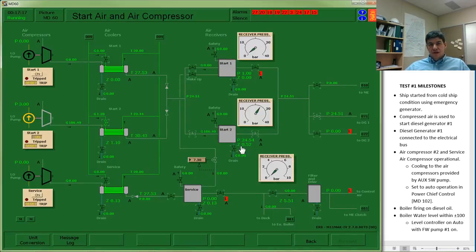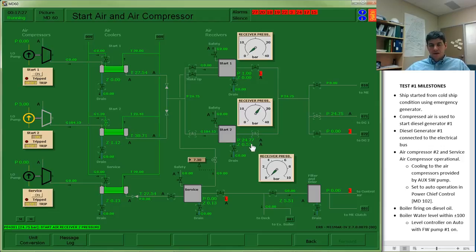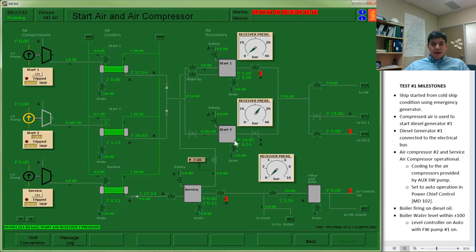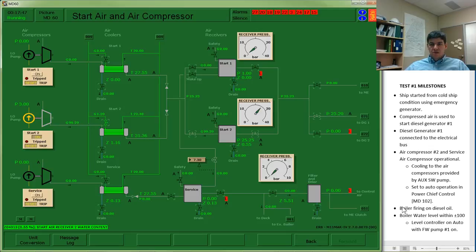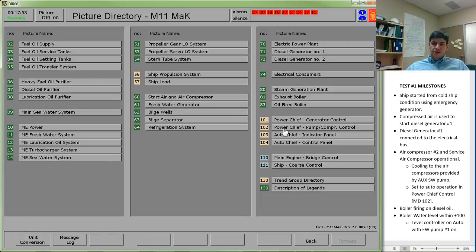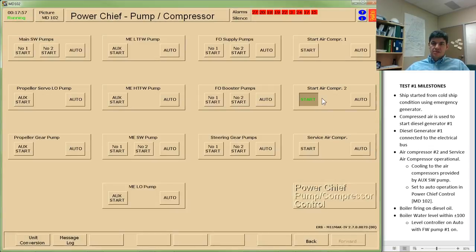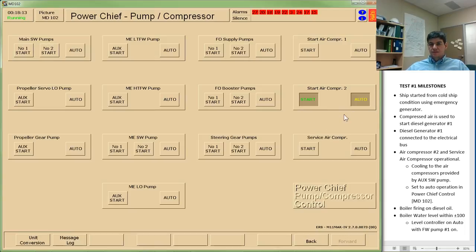So first of all, I'm still building up pressure. I target about 30 inside of either of the start air receivers. So I'm still on my way to getting there. What I want to be able to do is automatically turn that compressor off. So when he gets up to the pressure that he wants to be, I won't have to manually come and turn him off. I want it to be automated. That automation happens on page 102. So let's go there and just take a look. So PowerChief pump compressor control. And my start air compressor number 2 is on. And what I'm going to do is turn him into auto mode. And by turning him into auto, now the control system is deciding when to turn on or turn off the air compressor. So we don't have to make that decision anymore.